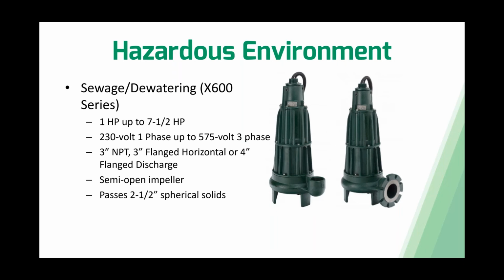So I'm going to stop here and just give you a 10,000 foot view, a quick difference between the vortex impeller versus a semi-open impeller. When you're talking about the vortex impeller, the vanes of the impeller do not come in contact with the fluid that's being pumped. It is a super reliable option. It's a non-clogging design, but typically it does lesser flow than a semi-open impeller. But again, it's not coming in contact with any of the fluid. It's creating that vortex and it's sucking up the fluids and pushing it out without actually hitting the impeller.